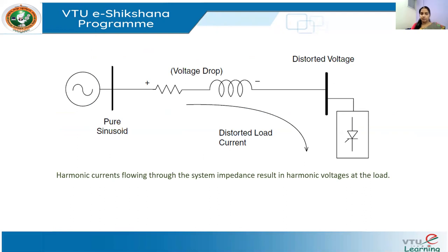Consider a system where the supply is a pure sine wave, connected through a linear power delivery system to a non-linear load — represented here as a power electronic converter in the shunt element. This figure shows how the current flowing through the system impedance results in both voltage distortion and current distortion. There is distorted voltage appearing on the load side.